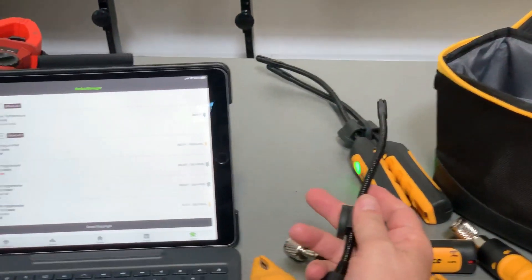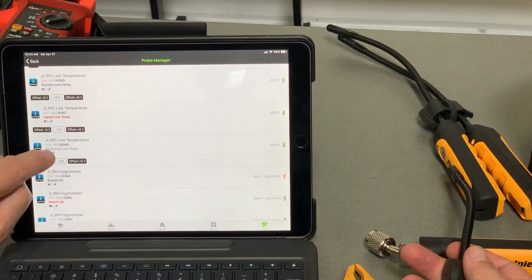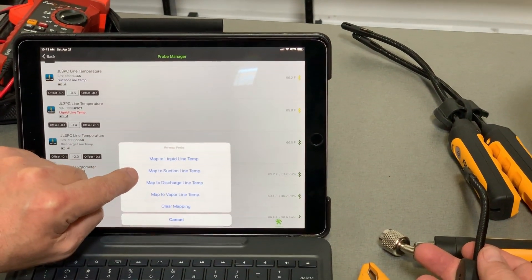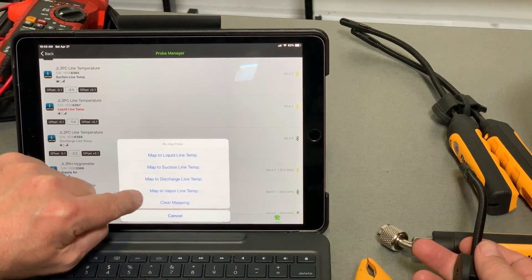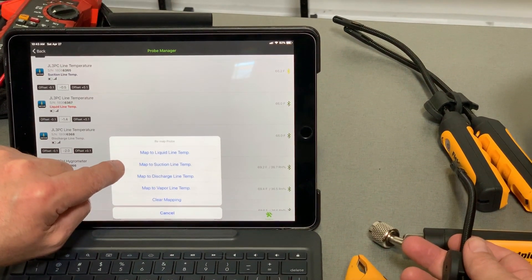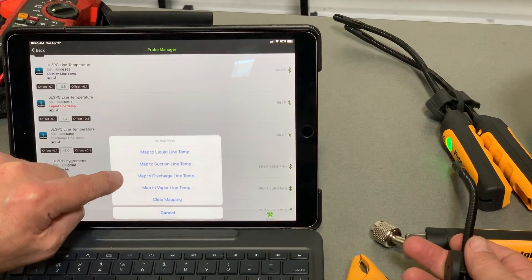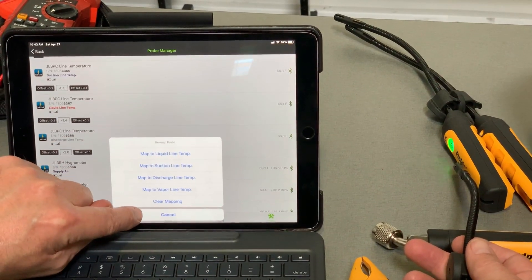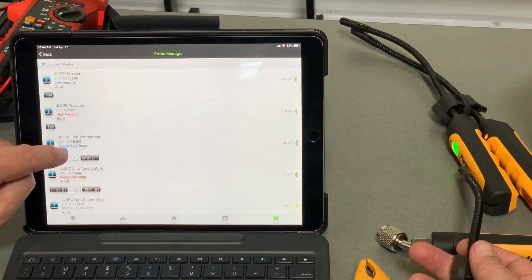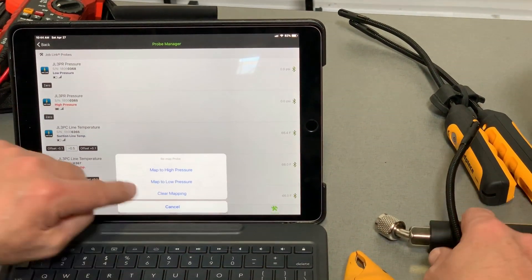You can see how everything's individual — these are all hygrometers here. And then if I get into my clamps, I can go to liquid line, suction line, discharge line, or vapor line. Vapor line is a true vapor line, like on a heat pump system. Suction line is for air conditioning. So if you have it tapped, you want to tell it where you have it on the system, and that helps with the diagnostics in MeasureQuick. These I can only map to high or low pressure, but that's how you get them all in.